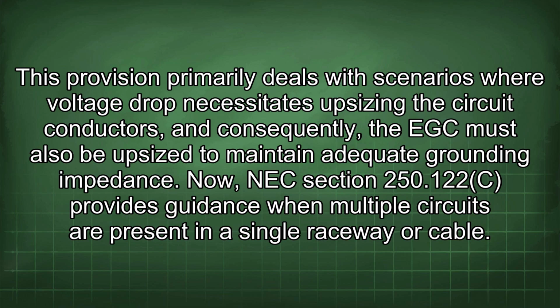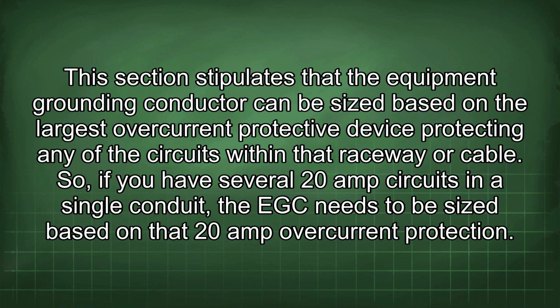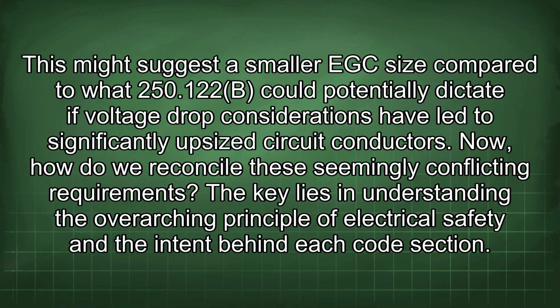Now, NEC Section 250.122(C) provides guidance when multiple circuits are present in a single raceway or cable. This section stipulates that the equipment grounding conductor can be sized based on the largest overcurrent protective device protecting any of the circuits within that raceway or cable. So, if you have several 20 amp circuits in a single conduit, the EGC needs to be sized based on that 20 amp overcurrent protection. This might suggest a smaller EGC size compared to what 250.122(B) could potentially dictate if voltage drop considerations have led to significantly upsized circuit conductors.